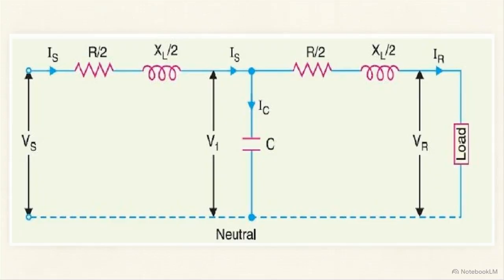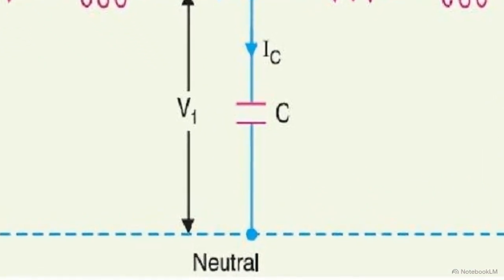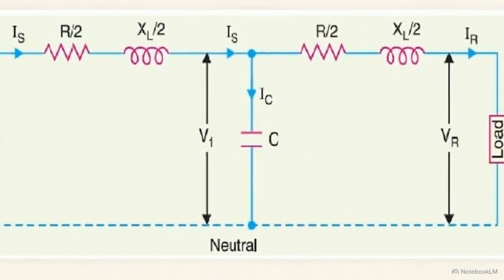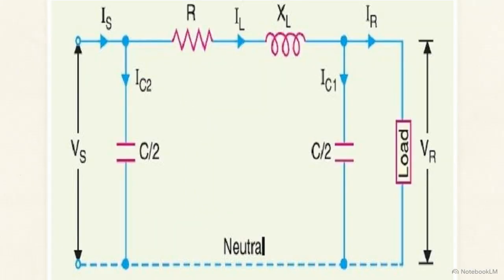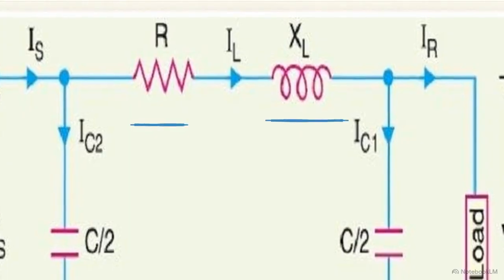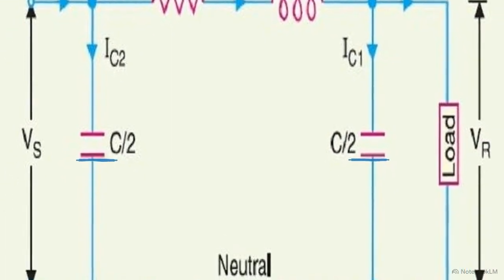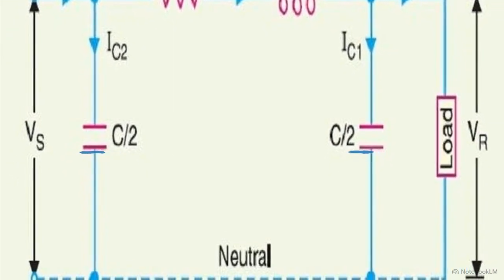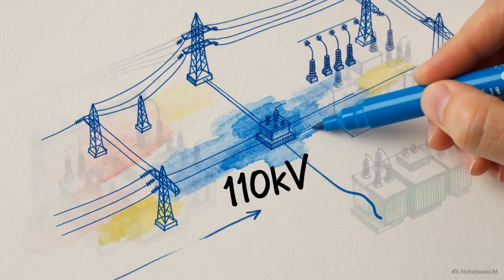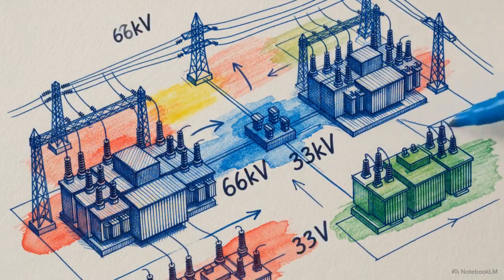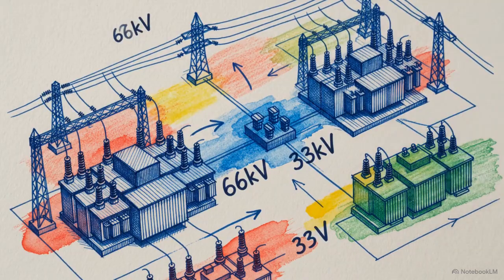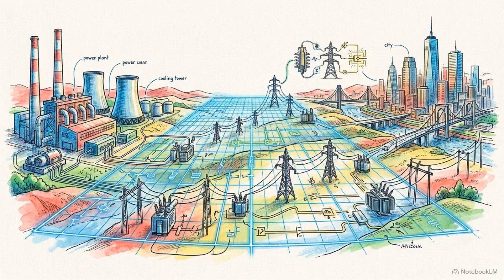This schematic shows the nominal T method, a common predictive model for medium-length lines. The T model mathematically concentrates the entire line's capacitance into a single midpoint, splitting the resistance and inductance in half on either side. Alternatively, engineers use the nominal pi method for different modeling requirements. The pi model concentrates the resistance and inductance in the center of the line, while splitting the capacitance into two equal halves at the sending and receiving ends. By solving the equations generated by these models, grid designers calculate the exact voltage drop across any distance before a single tower is built. These models serve as the blueprints that make the geographic distance between a plant and a city manageable.